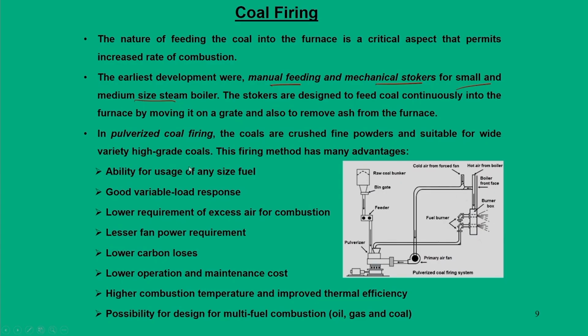That means, if you use pulverized coal firing, there will be lower carbon losses, lower operation and maintenance cost, then higher combustion temperature and improved thermal efficiency from the fuel burning. Then there is a possibility of design of multi-fuel combustion. That means this pulverized method of coal firing can be integrated with oil and gas as well.